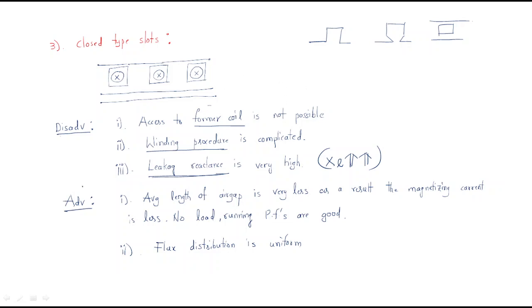The advantages of closed type slots: the average air gap length is very less. By doing this, the complete air gap decreases and as a result the magnetizing current is also very much reduced. No-load and running power factors are very good — both are improved significantly. Flux distribution is completely uniform. However, access to former coil is not possible, winding procedure is complicated, and leakage reactance is very high — these are the problems with closed type slots.